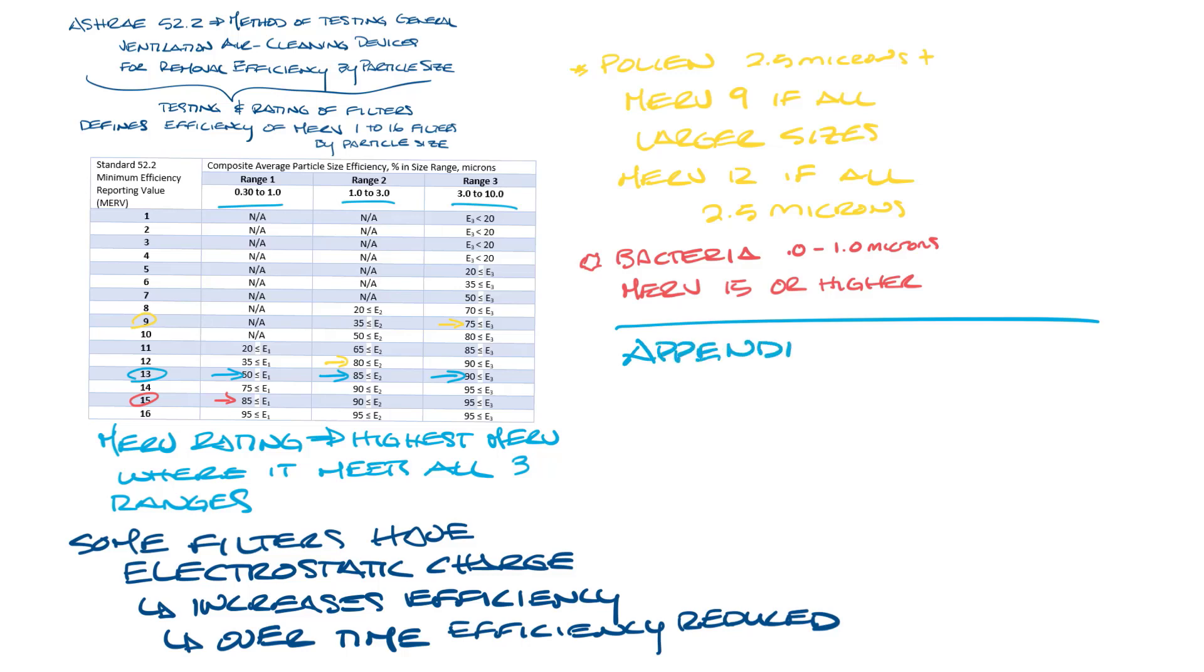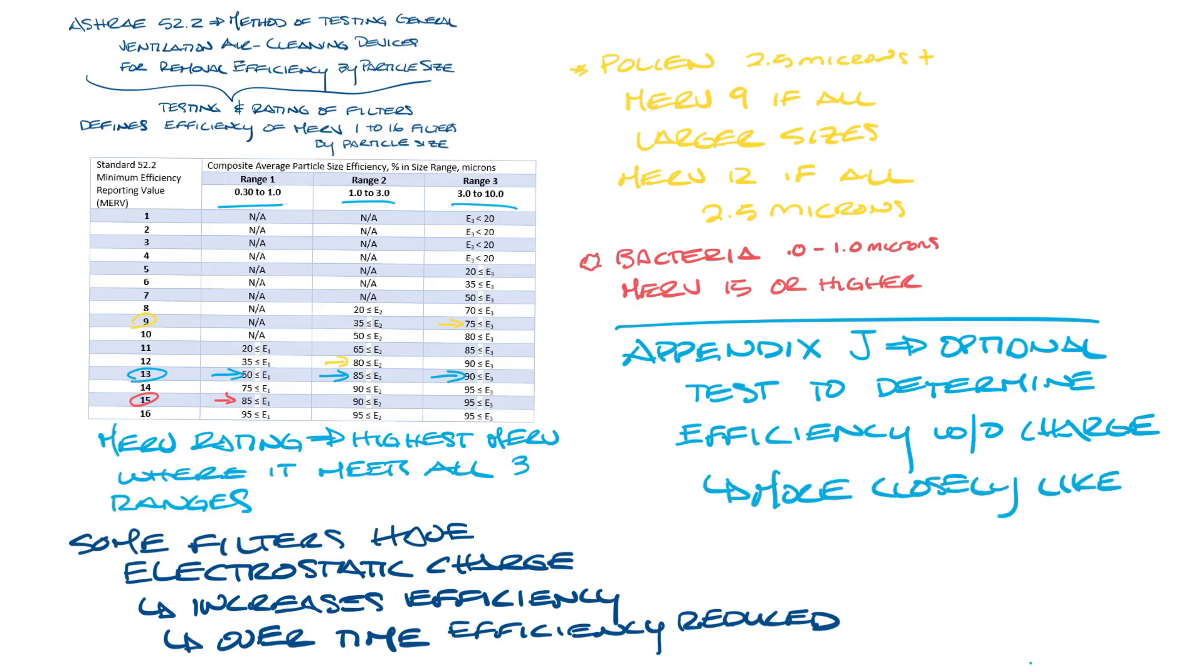ASHRAE 52.2 Appendix J has an optional test method for determining filter efficiency without electrostatic charge. The resulting values, denoted in MERV-A ratings, more closely represent the filter's efficiency in real use over time. Not all manufacturers do the Appendix J test, so you should be careful when you compare MERV ratings.